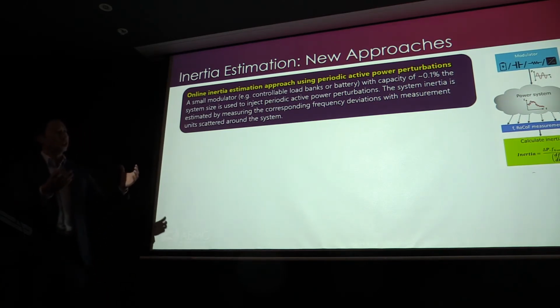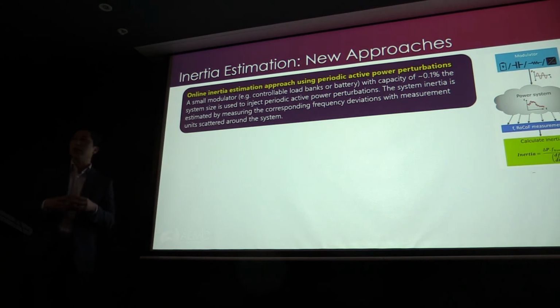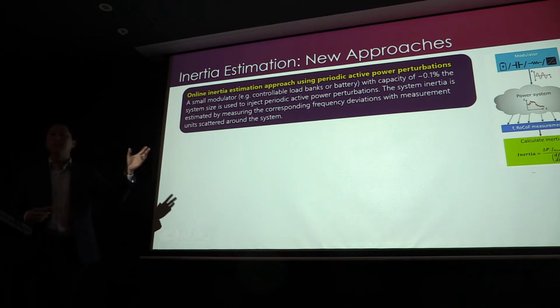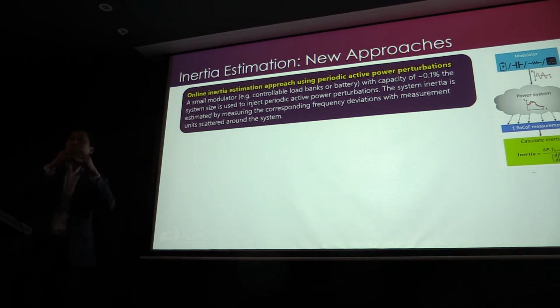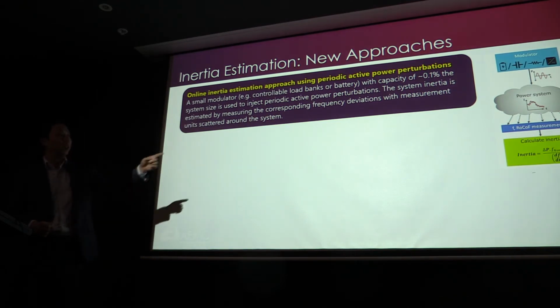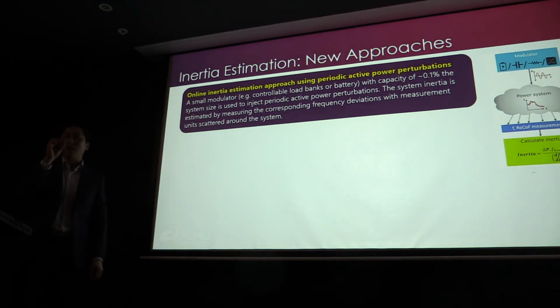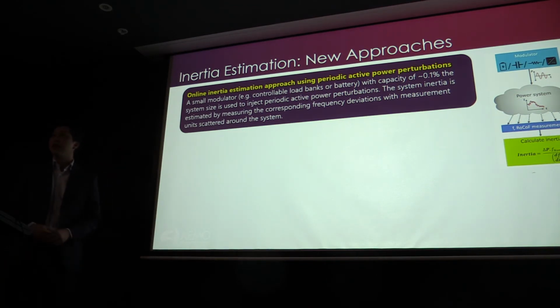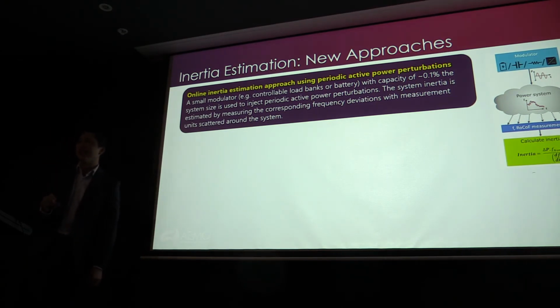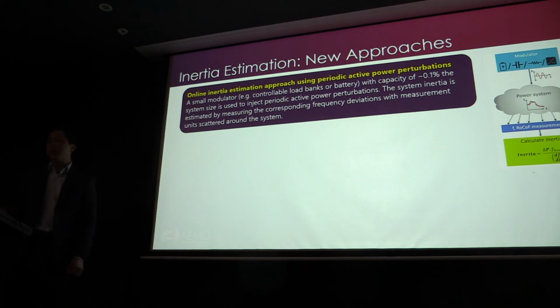And then what you can do is you can get very sensitive PMU measurements of the frequency in the power system, and then you can isolate out the frequency that you're actually oscillating at. With that, you can then use your simplified swing equation, because you know what injection you're using and you know your RoCoF, because you're measuring it from the frequency trace. So it's a controlled way of estimating inertia rather than using disturbances.